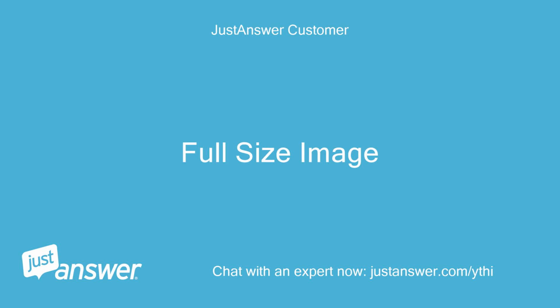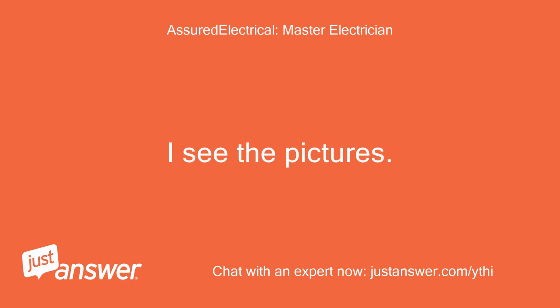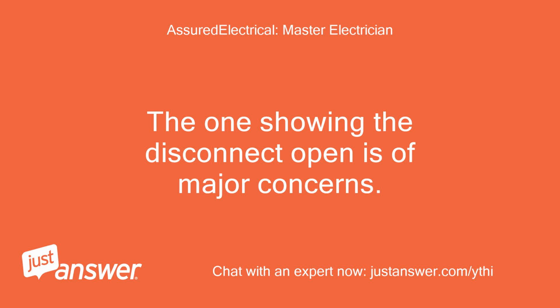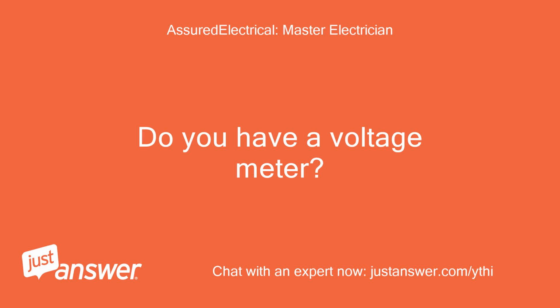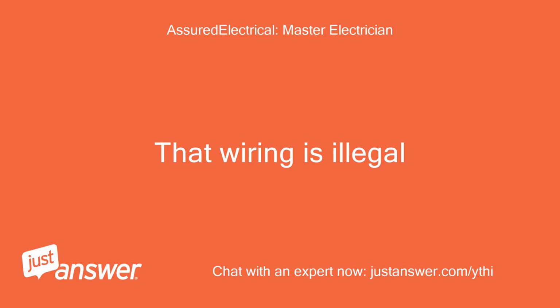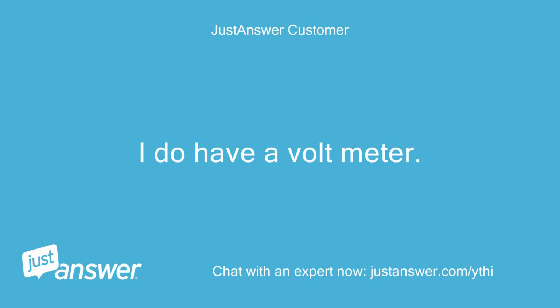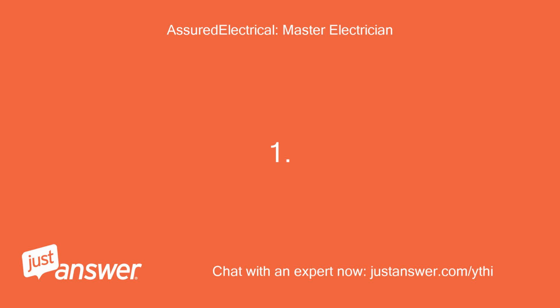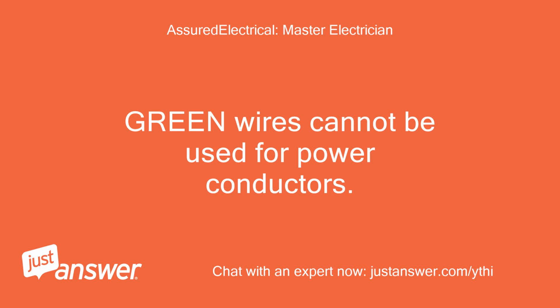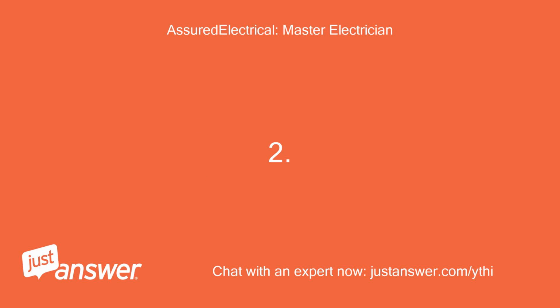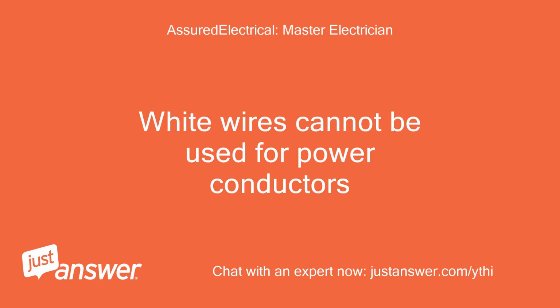I see the pictures. The one showing the disconnect open is of major concerns. Do you have a voltage meter? That wiring is illegal. I do have a voltmeter. 1. Green wires cannot be used for power conductors. 2. White wires cannot be used for power conductors.